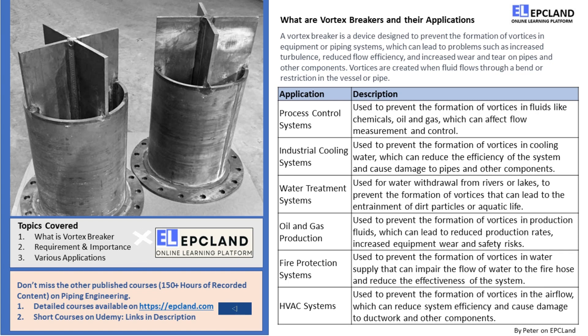Now, to understand the importance of vortex breakers, let's understand the effect of vortices on the flow. Vortices create an obstruction in the smooth flow, draw down gases inside it, and create a two-phase flow that has several drawbacks. Vortices disrupt the flow pattern inside the pipe or nozzle and can create erosion of pipes and fittings. The occurrence of a vortex in a fluid system leads to a reduction of pressure, increasing the requirement of pumping force. Therefore, it's crucial to avoid vortex formation in fluid systems.